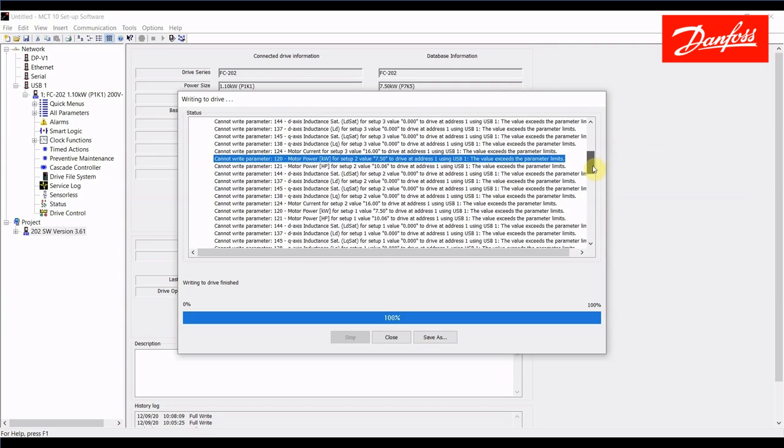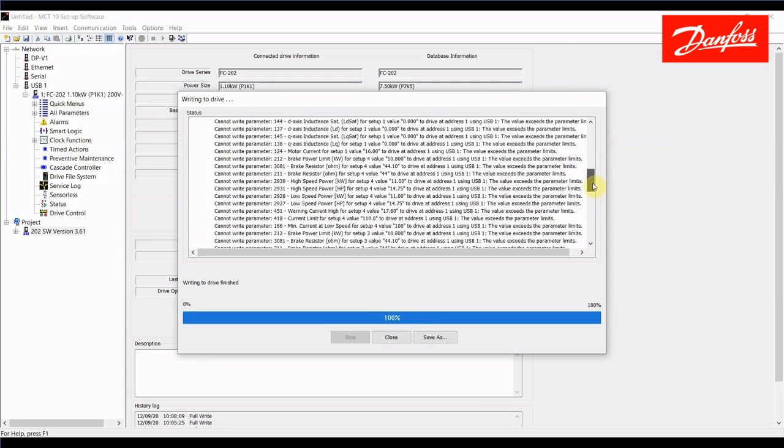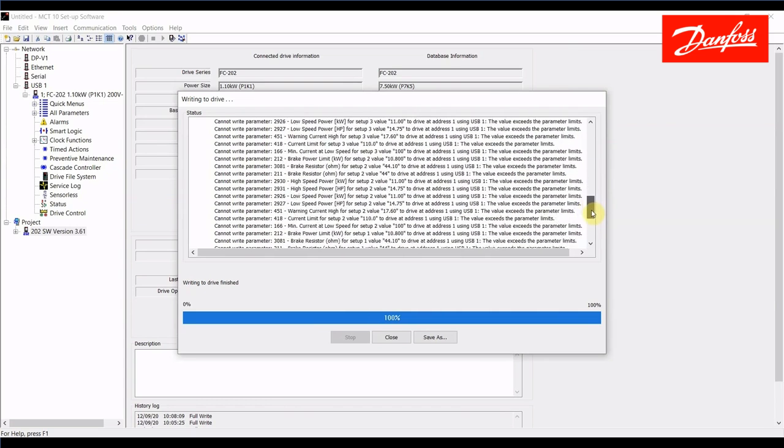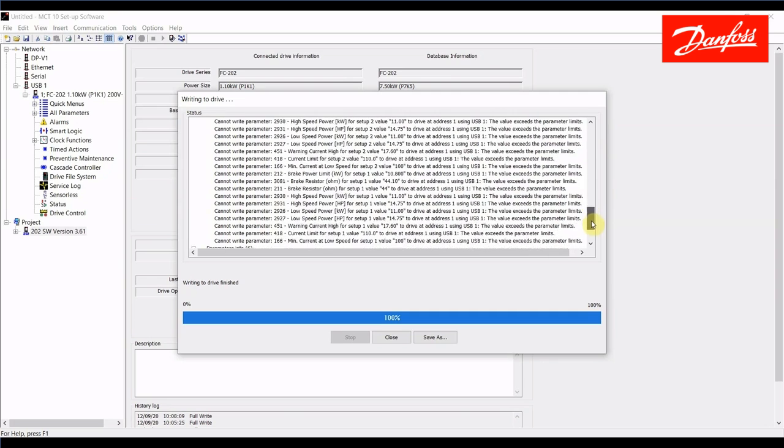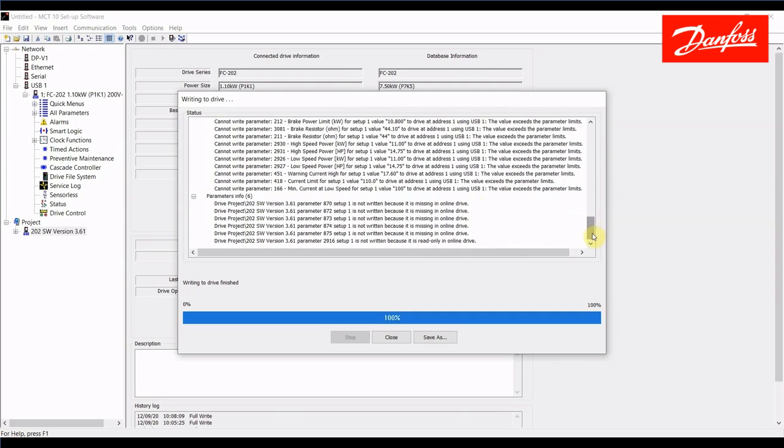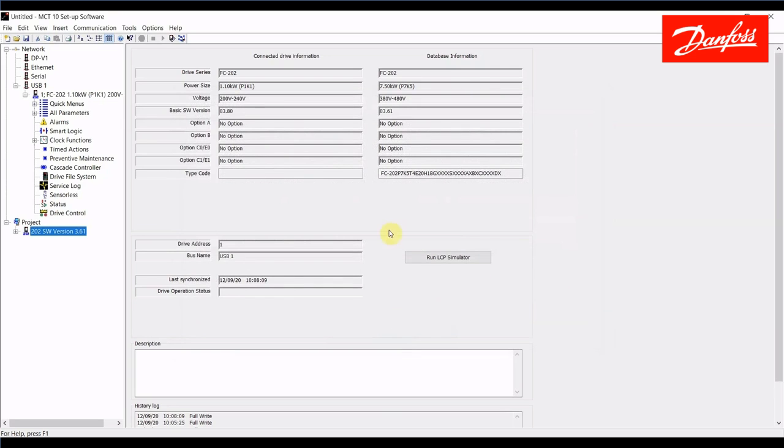You can normally disregard the motor parameters in the group 1 there. We have some things related to power tuning that I'm not concerned about and if we continue scrolling down we get here to this area where it shows the parameters that are not written. In this case these parameters here were not written to the online drive because that parameter is missing in the online drive. So you want to scroll through this list. Normally I'll say that you can accept these errors, go program the new motor data and test the setup to see if it works. Normally it will.